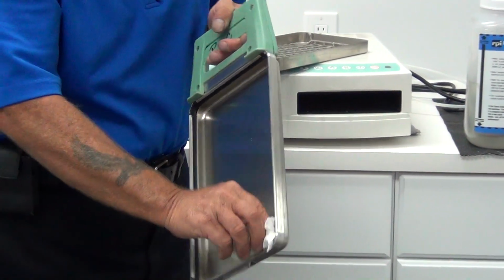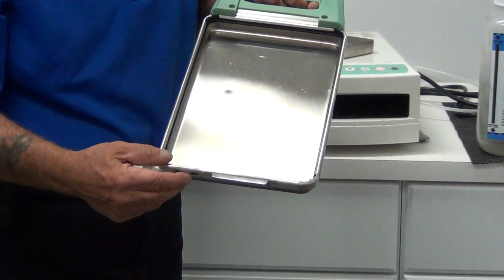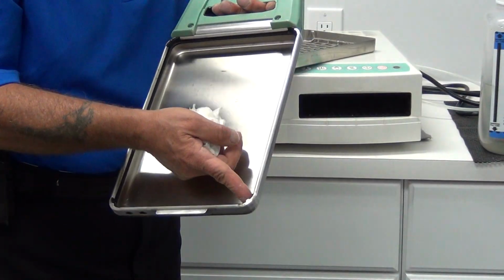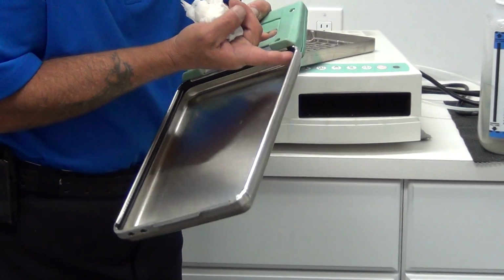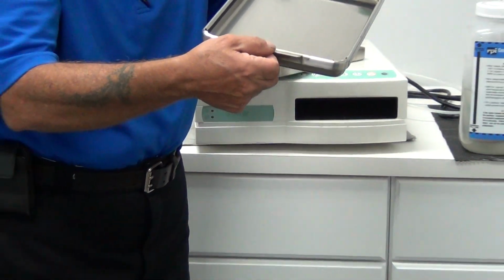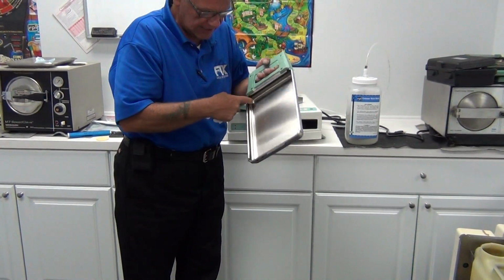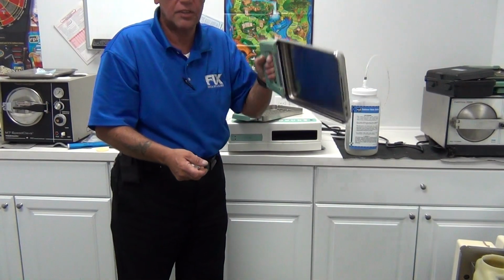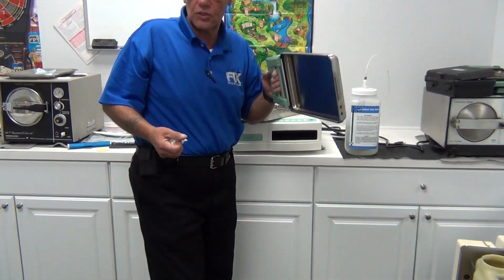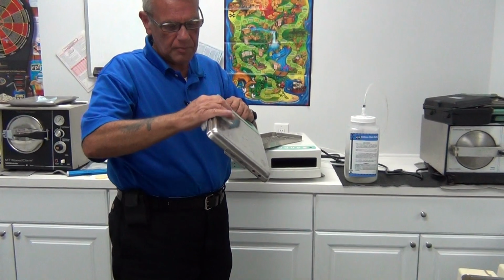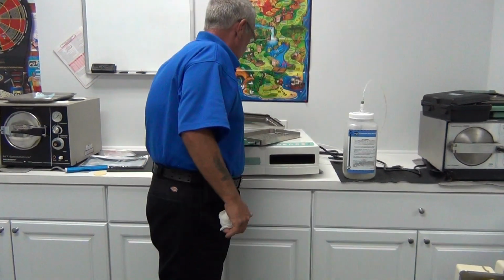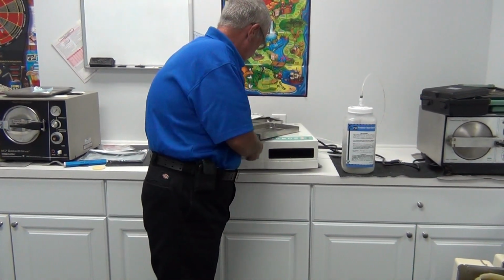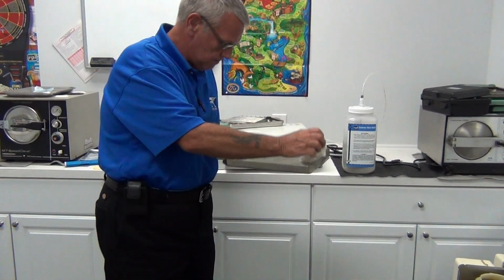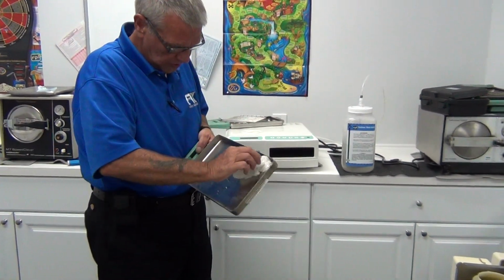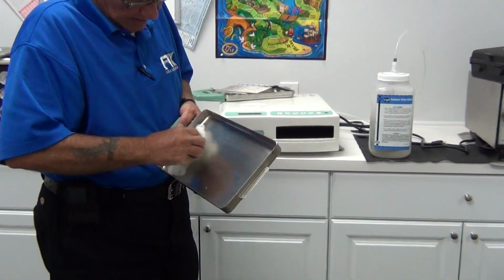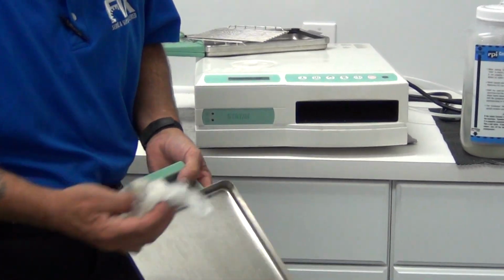What you want to do is wipe the cassette out and examine the gasket. We're going to look for tears, perforations, stretch spots, or saggy spots on the gasket. And the gasket looks pretty good on the top of the cassette. The cassette is a two-piece cassette, bottom and top. We'll lay the top aside, take the handpiece grate out, and check the bottom. We're still hot and we're still steamy, so we're going to be careful.